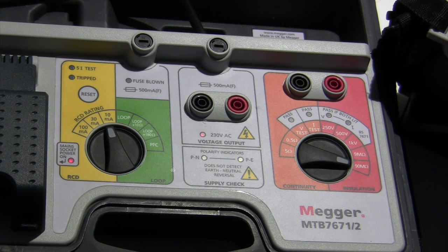What is it? Well, it allows me to test my multifunction testers, my Megger and my Fluke, to make sure that they are operating within prescribed parameters and that they haven't gone a bit screwy since their last calibration test. Now, obviously we have to have our testers calibrated every year, whether we like it or not. Unfortunately we don't, because it's often quite expensive to do.